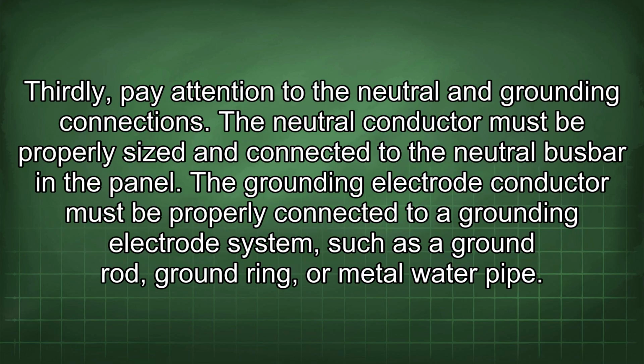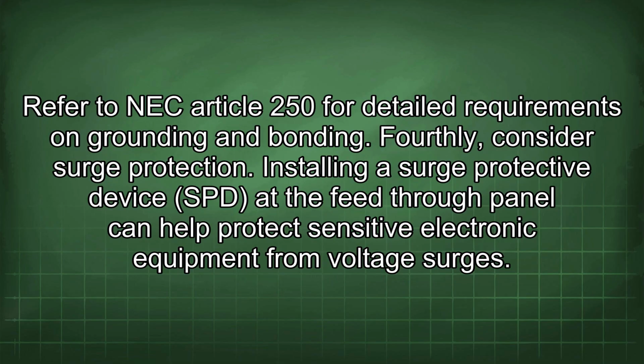Thirdly, pay attention to the neutral and grounding connections. The neutral conductor must be properly sized and connected to the neutral busbar in the panel. The grounding electrode conductor must be properly connected to a grounding electrode system, such as a ground rod, ground ring, or metal water pipe. Refer to NEC Article 250 for detailed requirements on grounding and bonding.